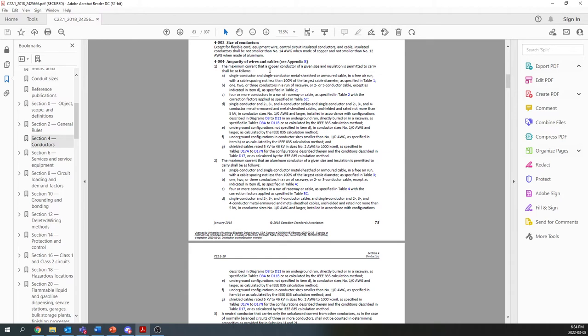And of course, aluminum cables are used in high voltage power transmission, but those are not covered in this document. So whenever ampacity is mentioned, you're generally always going to see one ampacity or one table for copper, one table for aluminum. So keep that in the back of your mind. You've got to always think about what conductor you are using.